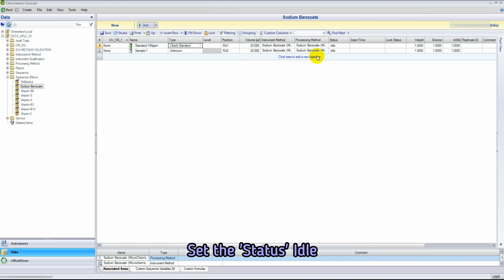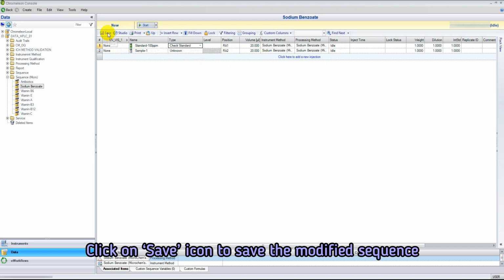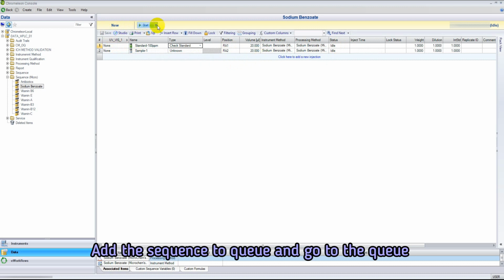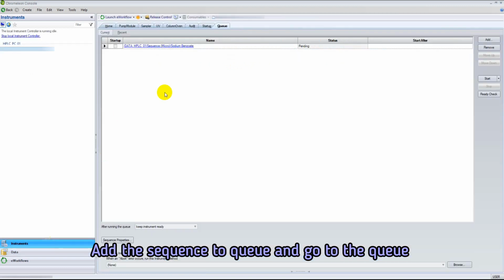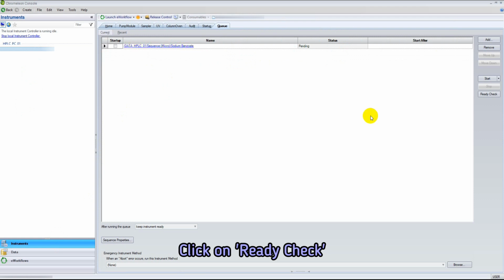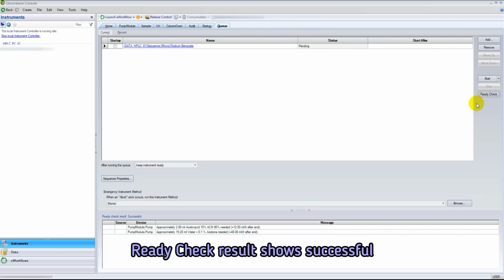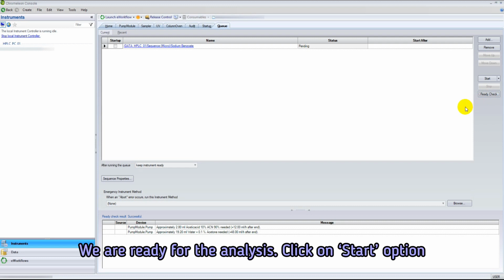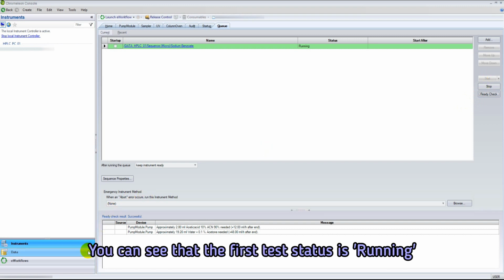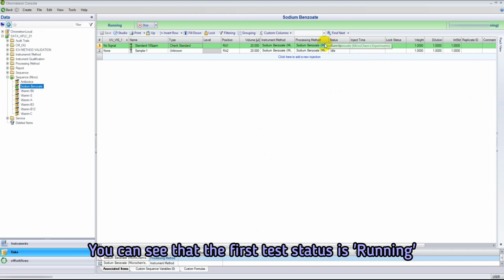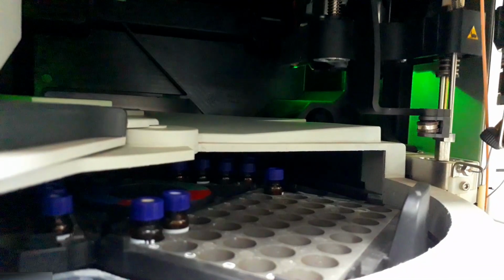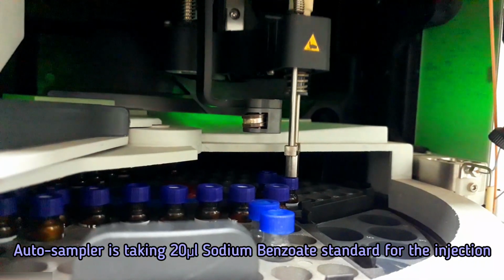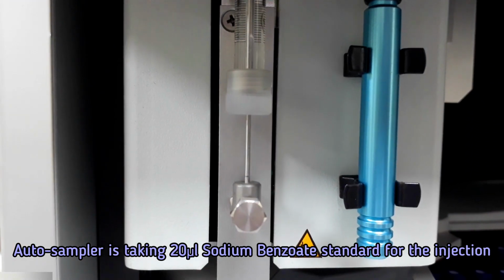Keep the injection volume at 20 microliter and keep the status idle. Save the sequence. Add the sequence to queue. Go to the queue and click on Ready Check. If the Ready Check result shows successful, then click on Start to start the instrumental analysis. You can see first test status is running. Auto sampler is taking 20 microliter standard for the injection from the position of RA1.